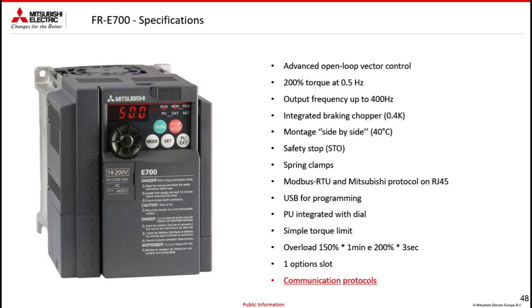First, however, if I had wanted to connect to the FR-D700 via software, but there had already been serial communication, I would have had to free myself from that communication, define the parameters at serial level to connect from my PC to the inverter and connect. Here on the FR-E700, it works on separate channels. There is always PU integrated with the dial, and the simple torque limit has been added so as to be able to limit the output torque.